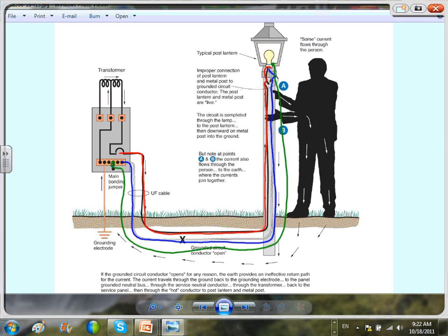If you have a short circuit, guys, line to ground, if you have a line to ground here, and Chad is holding on a hot conductor because that pole is defective, the current will go cook you first before it wakes up the circuit breaker. Why? Because of the high impedance in the ground. Why do you think we send the second wire? If you send the second wire, suppose accidentally that hot touches the ground for whatever reason. This is a piece of copper going direct from the source into the load. That copper makes the current so high that the circuit breaker will open immediately. Who cares? You're not going to be electrocuted.